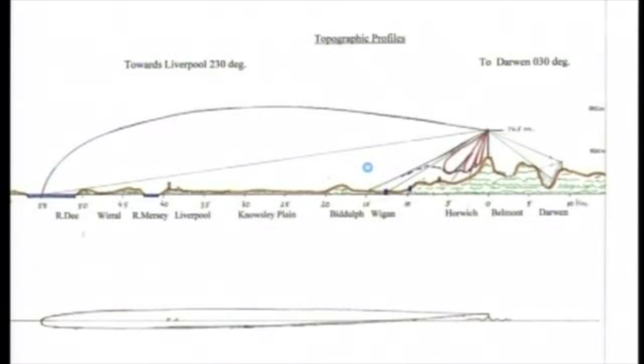This is the topographic profile towards Liverpool. The main beam hits the ground at about the distance of Wigan and continues at good strength over the Knowsley Plain and over Liverpool. Note the two cathedrals, then over the Mersey, the Wirral Peninsula and the Dee Estuary, just reaching the north Wales coast at its receivable limit. Closer to Winter Hill, before the main beam touches ground, service is by side lobe radiation. The nulls between the side lobes are filled by carefully adjusting the phase of the feeds to the aerial panels — very necessary to provide a service in the nearby areas of Horwich and northern parts of Bolton.